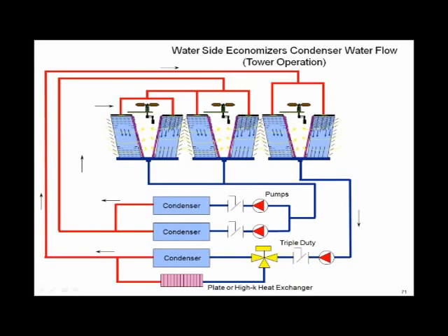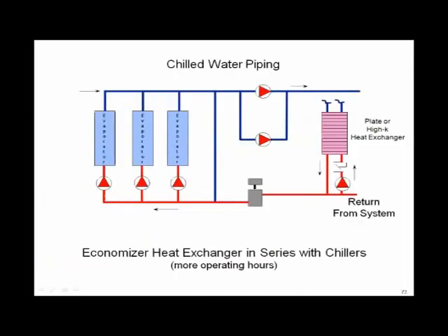But you've got to pay attention to head pressure control, and you've got to pay attention to this because the code said what? Integrate. Be able to run the chillers at the same time you're running the waterside economizer. So that impacts how you do your towers. We're going to suggest this is probably what you're going to wind up doing. You make your own decisions, but this is what we're seeing a lot of people go to.